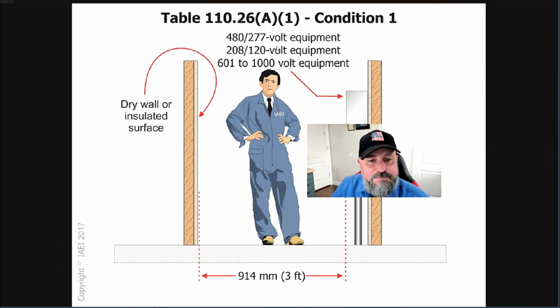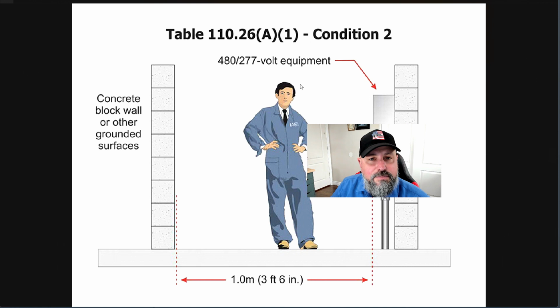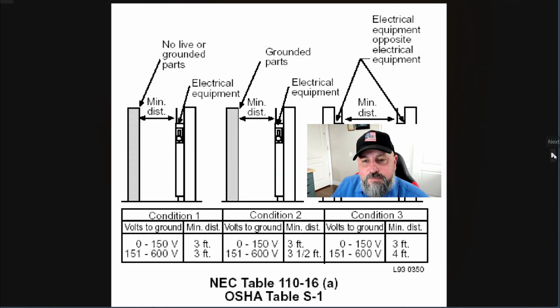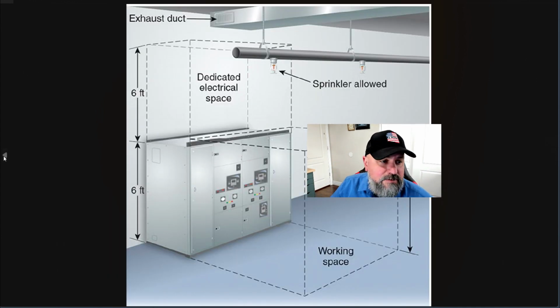Drywall or insulated surface. So 3 feet. We got that from here to here. So this is considered grounded equipment, right? Or grounded material, because it's block or it's going to be concrete. So you're going to need 3 feet 6 inches on 480/277 volt. And here's another graph for that. No live grounded parts, minimum distance, 3 feet. Condition 1, grounded parts right here, 0 to 150, 3 feet, 151 to 600 volt, 3.5 feet. And then electrical equipment opposite electrical equipment. And that's condition 3, 0 to 150 volt, 3 feet, 151 to 600 volt, 4 feet. All right, that's going to be the next one. We'll go over that next.